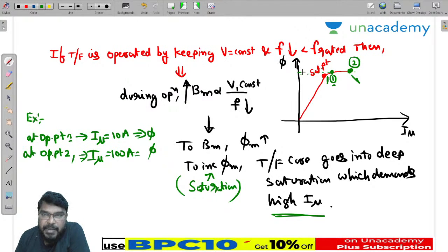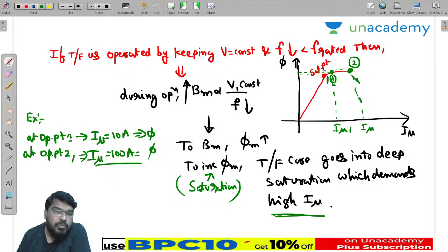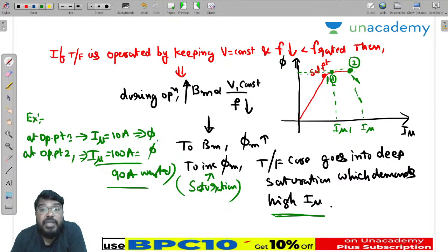How much change in flux is there? It's almost constant, but the magnetizing current requirement, I1 and I2, I2 equals 100. So 90 amps of current is wasted to create the same amount of flux. That's why we have to operate the transformer at rated voltage and rated frequency.